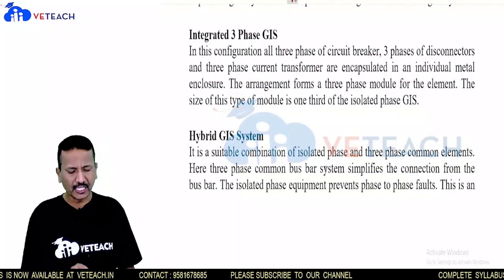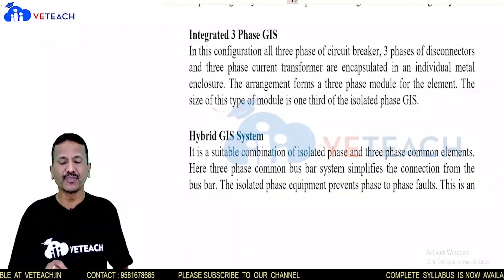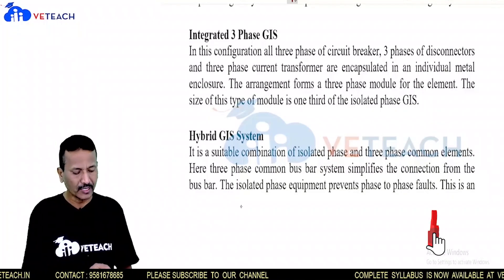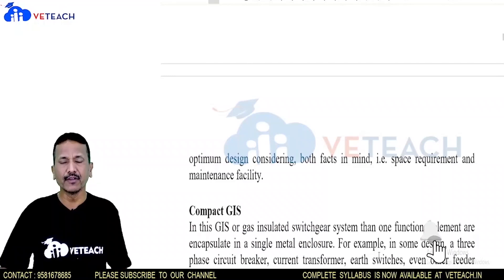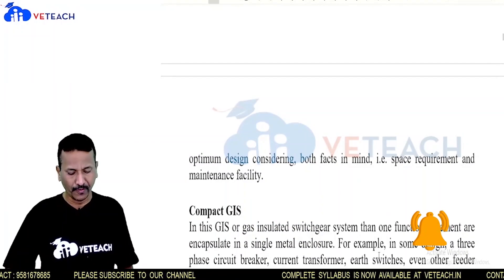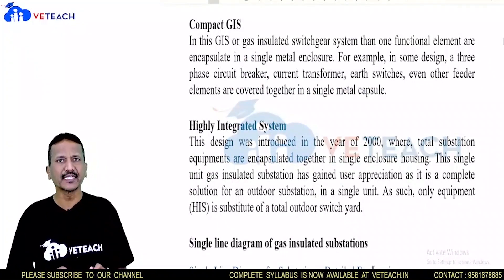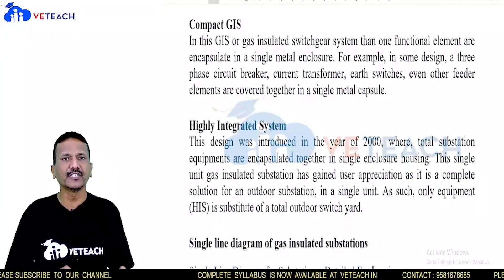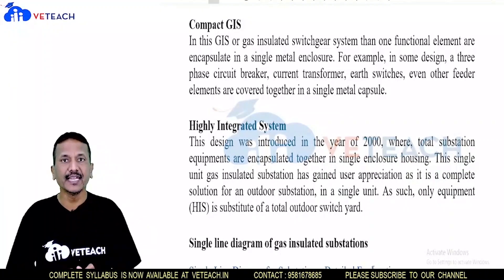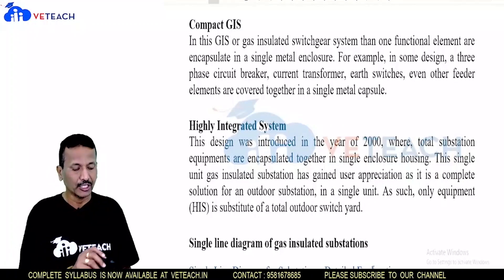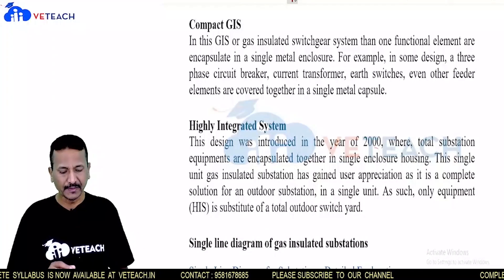The hybrid GIS is a suitable combination of isolated phase and three-phase common elements. Three-phase common bus bars simplify the connections. The isolated phase arrangement prevents phase-to-phase faults. The fourth type is compact GIS, and the fifth is the highly integrated system.